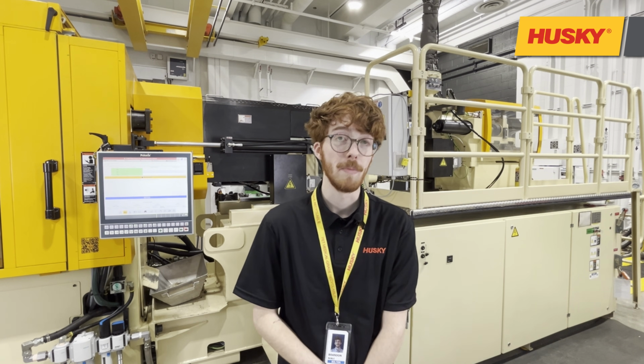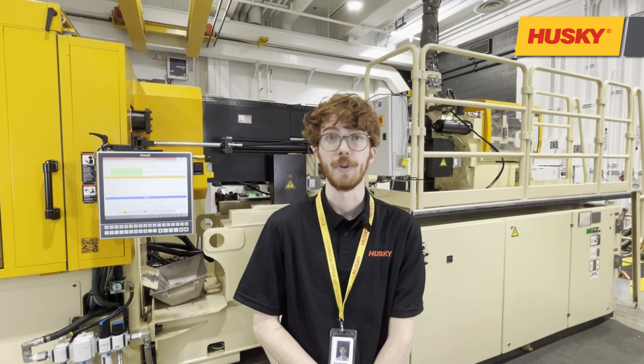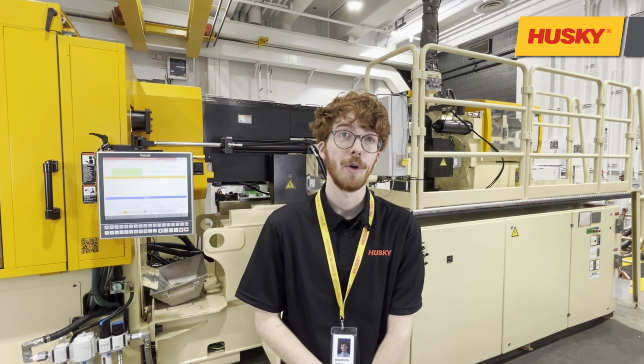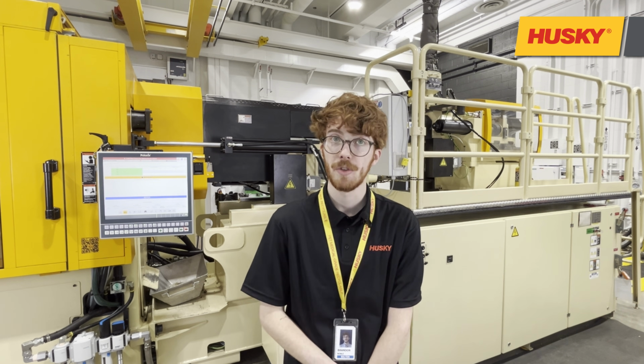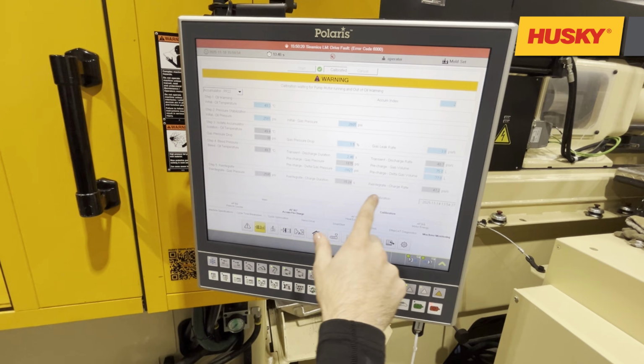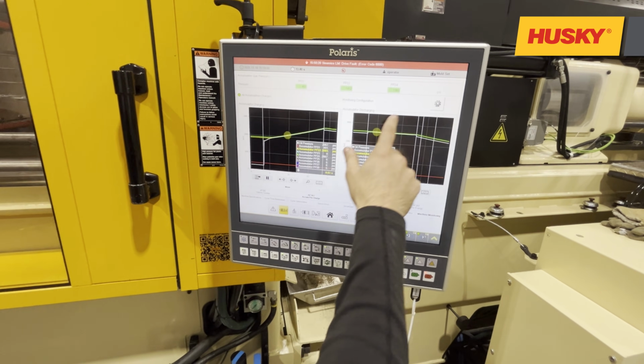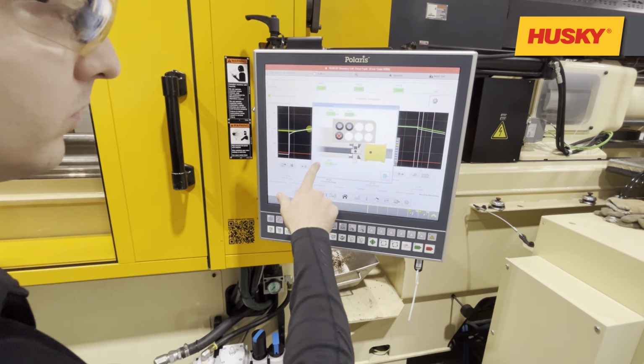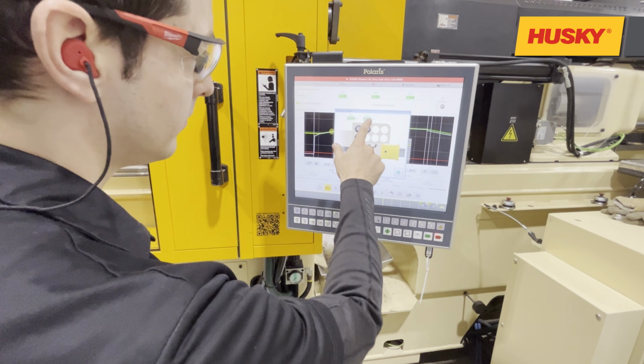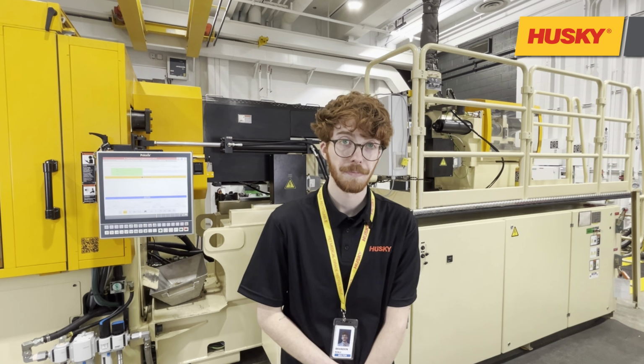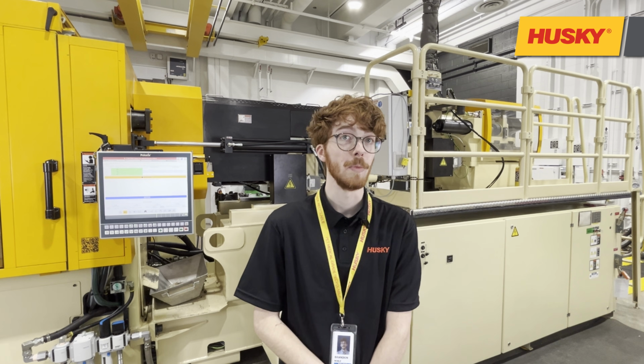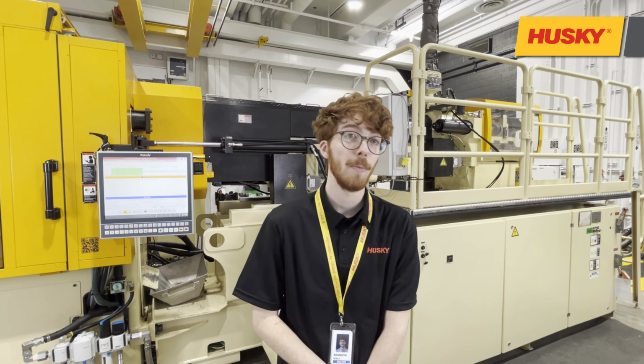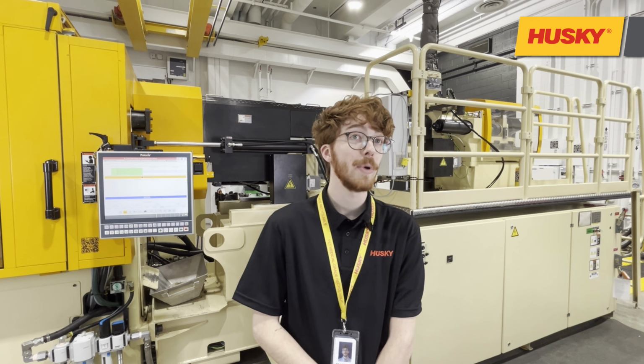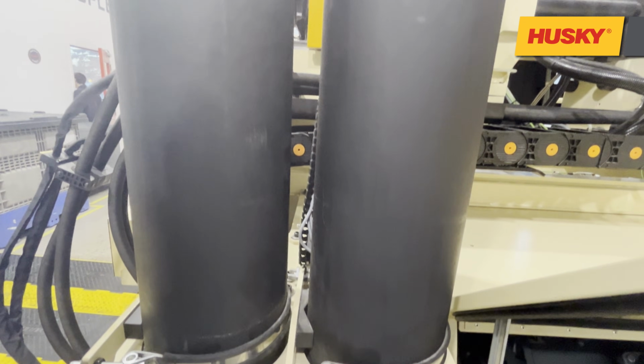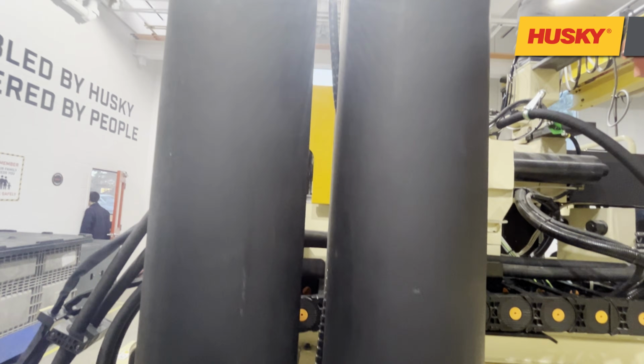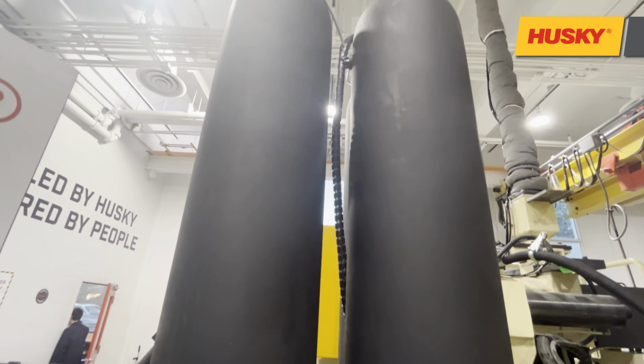When the pump starts, we measure the pre-charge levels and the charge time for each accumulator. If combined with the Power Pack motor monitoring package, we can also measure the energy required to charge the accumulators. When the pump stops, we measure the internal leakage in the system. This allows us to detect worn seals, valves, and study the flow through the hydraulic circuit. By combining measurements from the accumulator charging, discharging, and the Power Pack motor monitoring package, we gain a comprehensive overview of the entire hydraulic system. This gives us critical insight into machine health and predictive information to prevent issues before they happen.